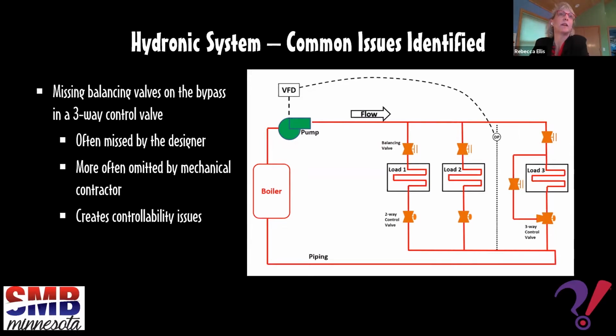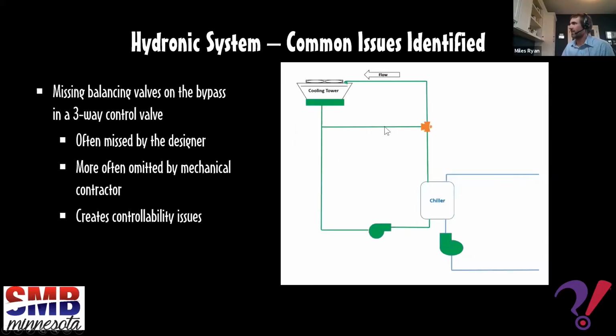No, you said that, that's what you said. But I'm saying if the boiler minimum flow is 150, then you would set that valve for 150. Oh yeah, I guess that could be a case. And then also, if the boiler's minimum is 150, it's very likely that you have multiple bypass lines out in the system, either multiple three-way control valves or a separate dedicated bypass line with a control valve on it.